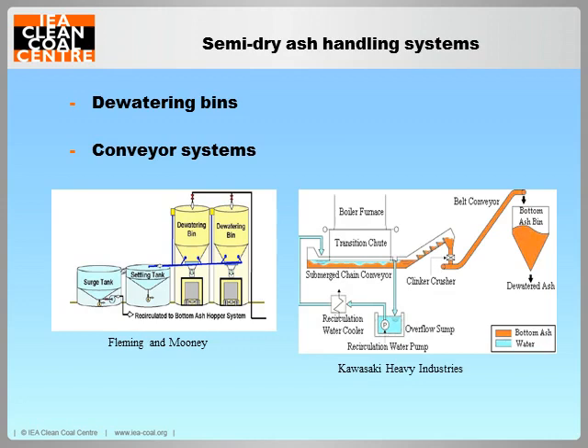Now, in a dewatering bin system, two bins are needed, and these are used alternately. The bottom ash slurry from the ash hopper is pumped into the top of the bin, and when the ash level reaches a certain point, the flow is stopped. The water is then passed through decanting screens into a separate settling tank. Here, the remaining ash particles are removed and returned to the dewatering bins, and the clear water is then stored in the surge tank before its eventual return to the ash hopper.